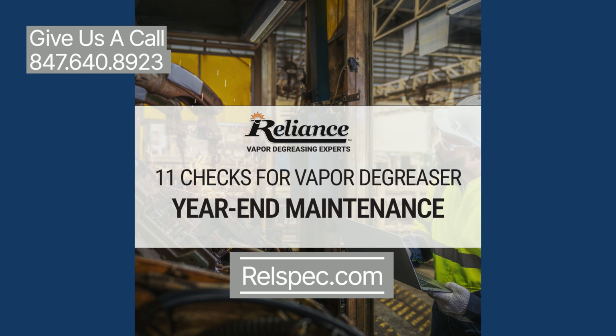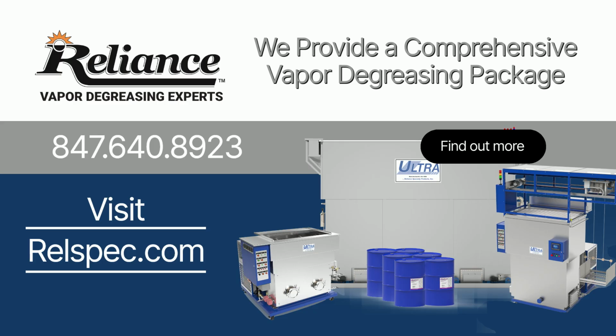Conclusion. The holidays are a great time to do yearly maintenance on your vapor degreaser. They say an ounce of prevention is worth a pound of cure. Taking the time at the end of the year to walk around the tank to check for leaks, clean and inspect the refrigeration systems, and clean the heaters would be the minimum to do. And doing these 11 maintenance checks and inspection steps of your vapor degreasing equipment will help reduce downtime and minimize quality issues for the year ahead.